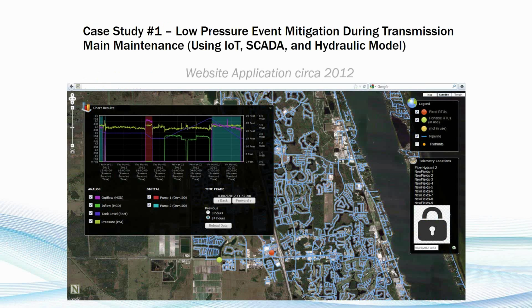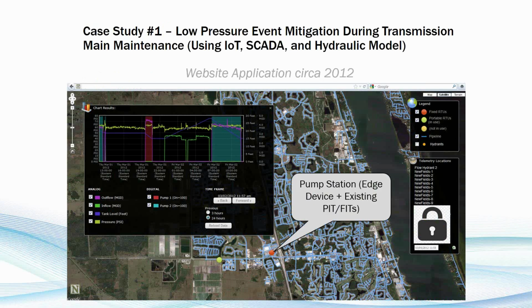This shows the website application circa 2012, which was pretty nice at the time. You can see a trend chart for the pump station, reporting pump station inflows and outflows, tank levels and pressures, and pump status. These are all existing instruments at the pump station, and we just piggyback on those signals without being on the SCADA network.